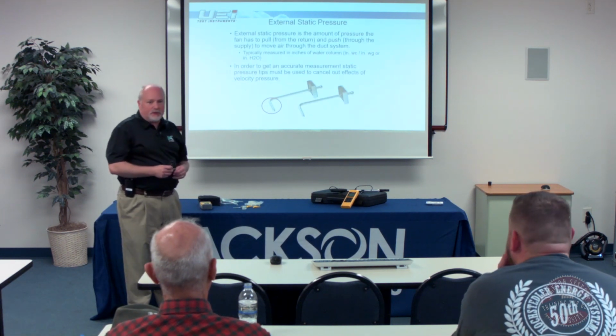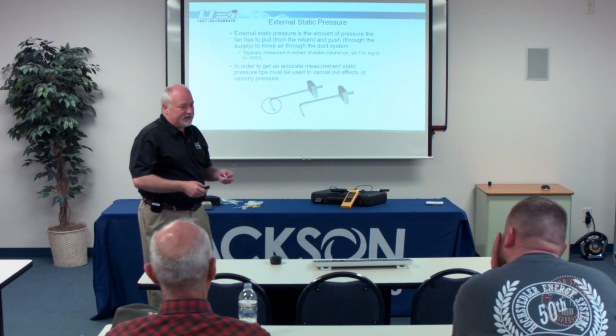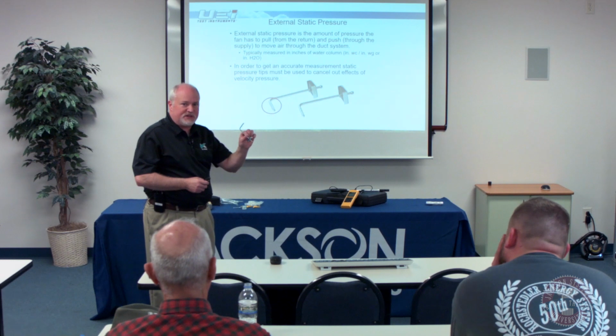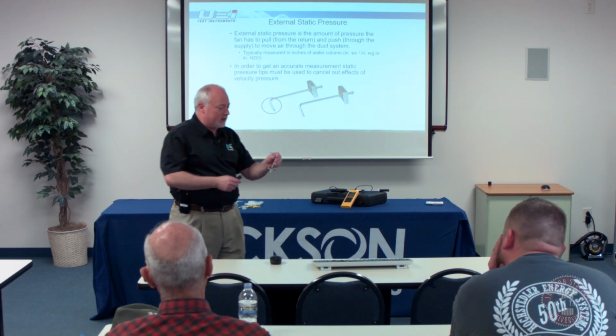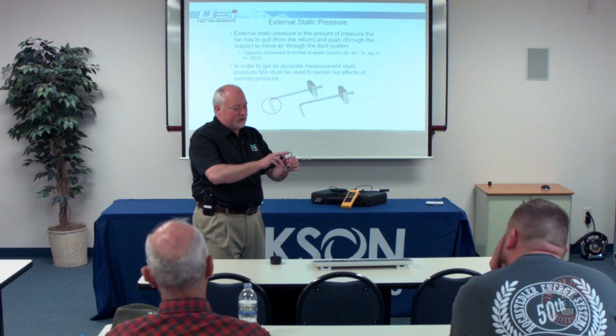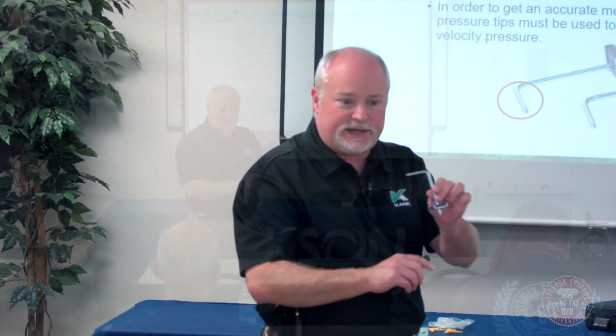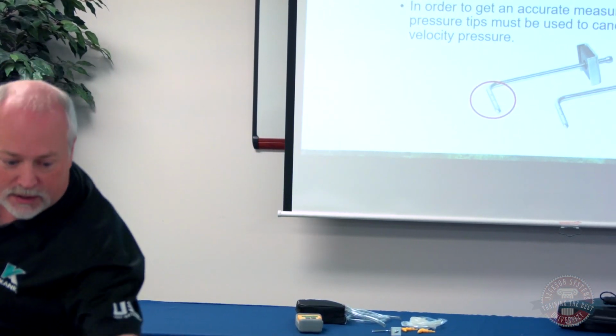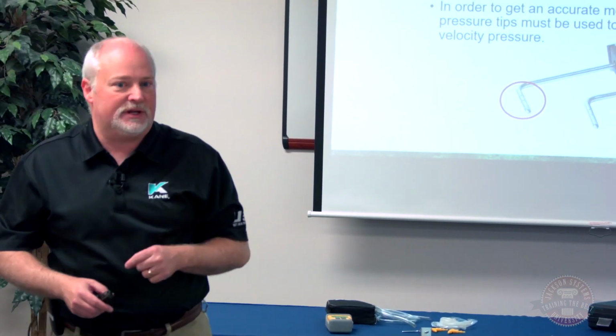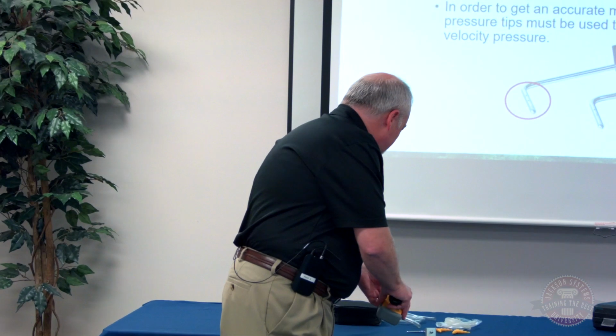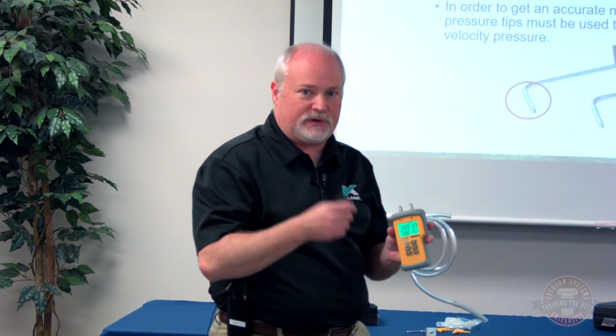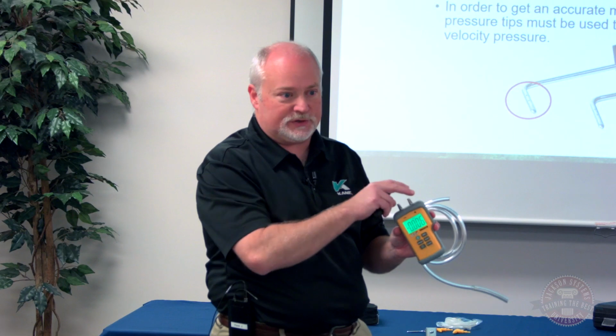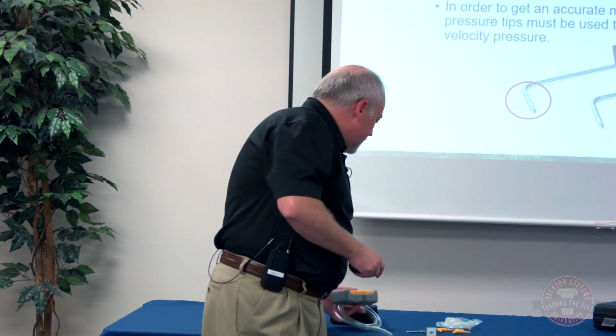Okay. Anytime we want to check external static pressure in a piece of equipment, it's important that we use static pressure tips. And the reason being, if you look at these, I know it's probably not going to show up real well on the picture, but when you have these, you'll notice that there are small holes in both sides of those tips. And the reason for that is that it eliminates the velocity pressure. If I were to take this manometer, put the hose on it, and then blow in the end of the hose, I could actually change that just because I'm blowing in the end of the hose. The velocity of that air is going to add pressure to that manometer, so it's going to add a reading. But when I'm checking static pressure, I don't want to include the velocity of the airflow. I want to know how much pressure that duct is seeing.